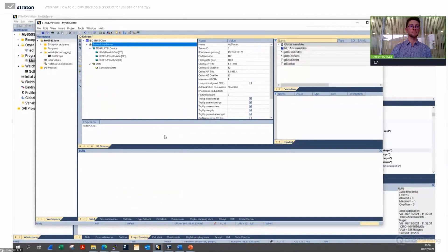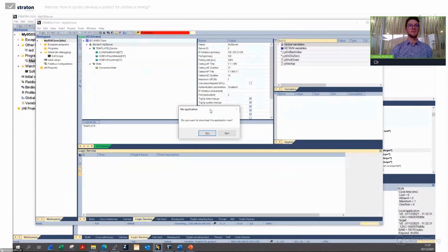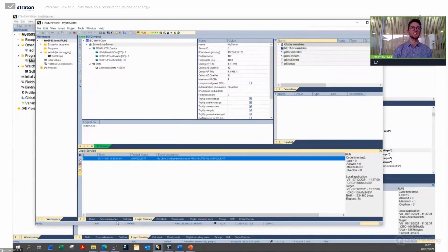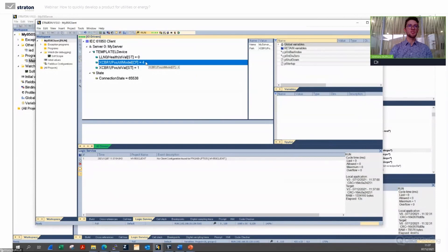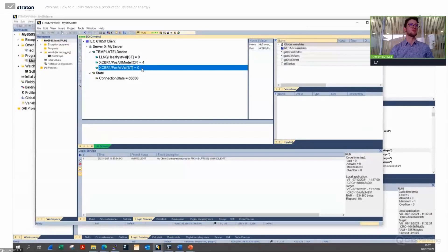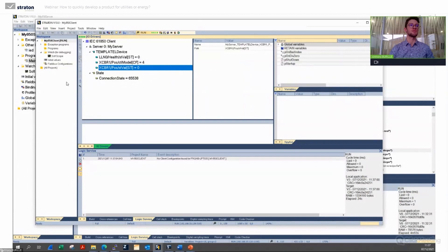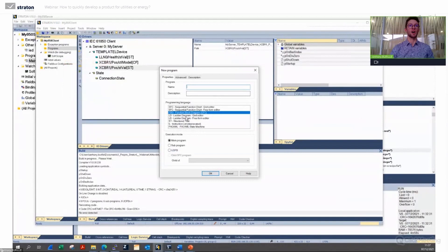I can see everything — even more than on the server side — including information about buffered report control blocks and unbuffered report control blocks. I can access the health of the logical device, the circuit breaker position, the circuit breaker control model. I click OK, it creates the architecture tree automatically. I can insert a status variable to be sure I'm connected to the server. I build the application, go online, download it to another runtime on my PC, and I can see it's connected correctly — the control model and position written earlier are correct, circuit breaker position is blinking, connection status is fine.